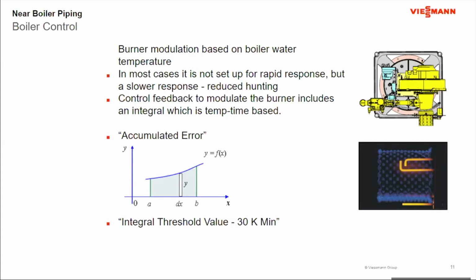Now, when we look at the operation of that burner and the decision on when to change the firing rate, or modulate, it's all about the feedback from the control circuit. In this feedback for the control circuit, one of the factors involved is what's called an integral. An integral is one of the key pieces of the error loop for the feedback circuit.